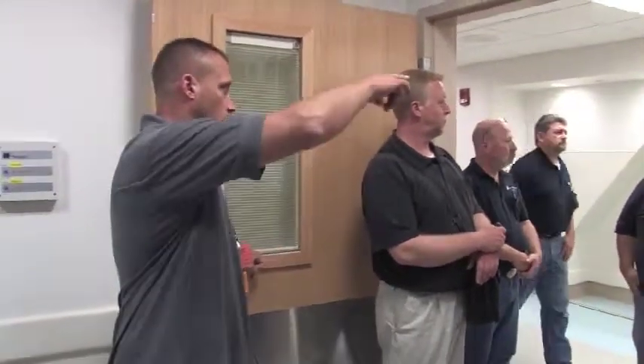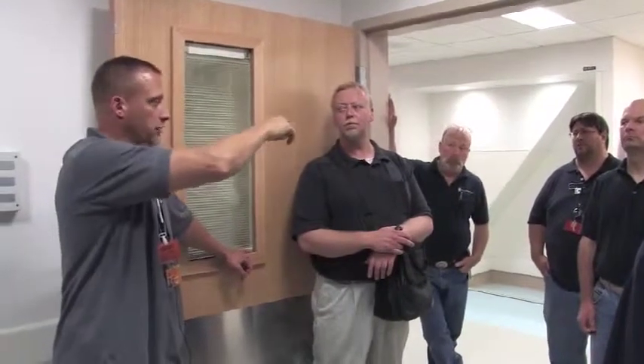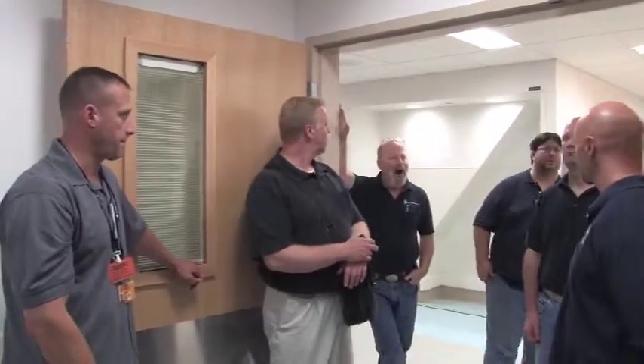So that's pretty much it. Any questions about where anything else goes? Good. So it's only in this room to isolate if you get a leak out there outside. Or you can shut this floor off, same thing. This right here will isolate your return coming back. Your control valve is isolated here. But your two shutoffs for the floors are right at the bottom of the riser in that room. Yeah, that's the easiest way, shut it down there. Somebody might be in this room. Yep.